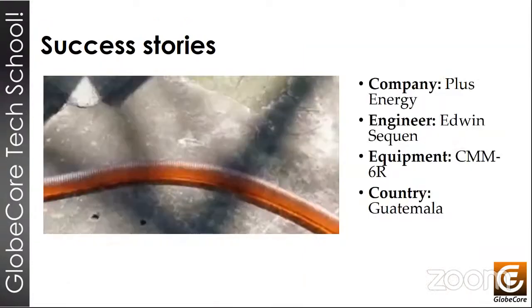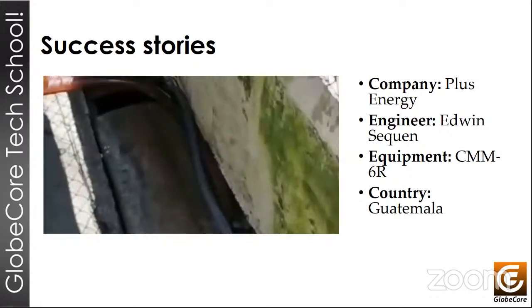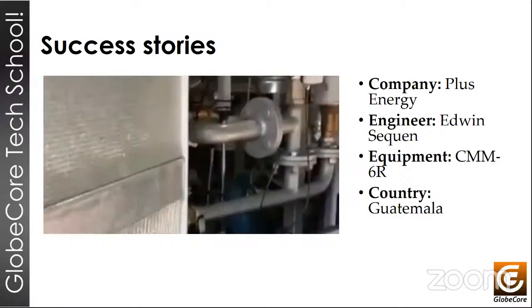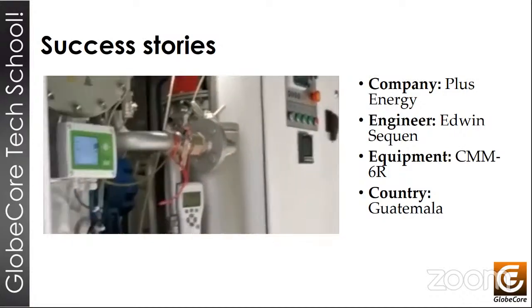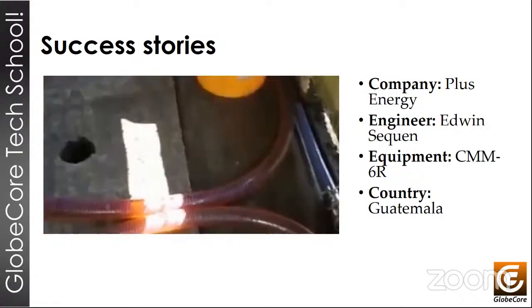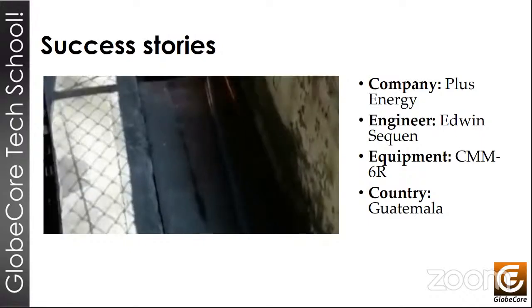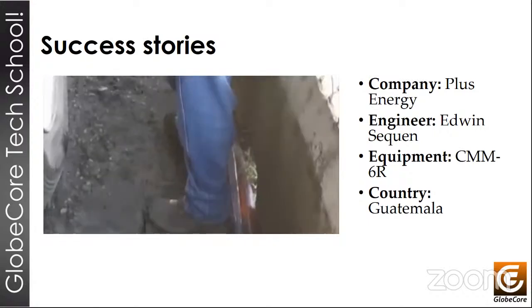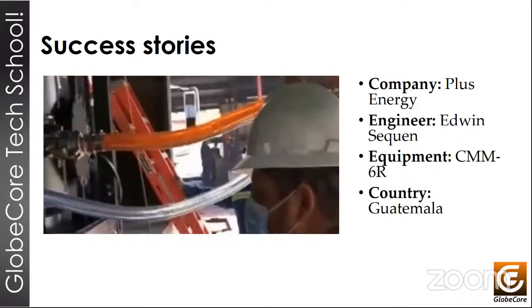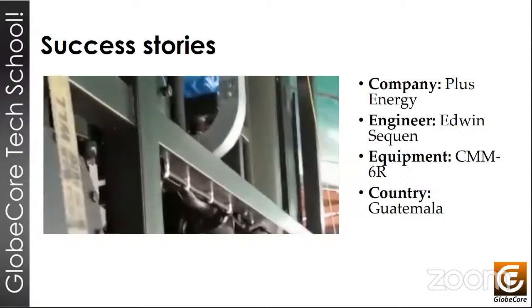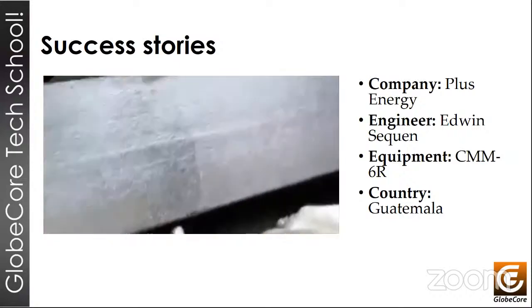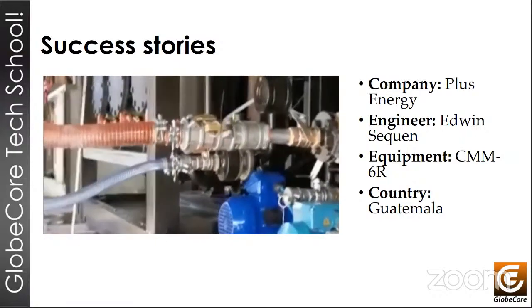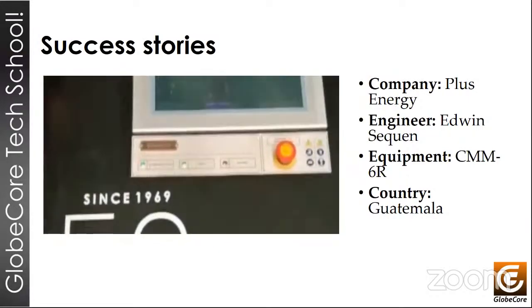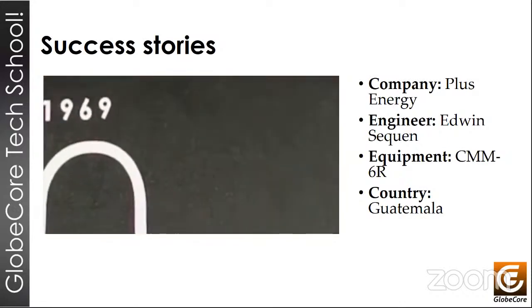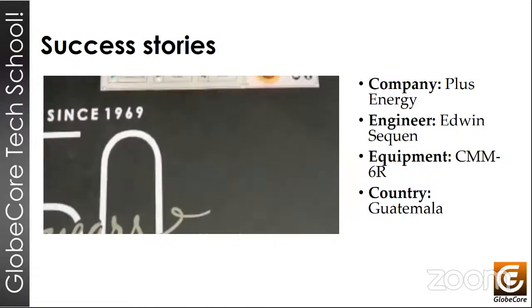Next slide, please. And here we have a little video. This is a project that was done in Guatemala. If you look at the two hoses in the video, you will see the darker one goes into the regeneration plant. This was a 6-column machine with 6 columns of Fuller's earth. Also, this plant includes a vacuum degasser for purification. These columns contain Fuller's earth, and towards the end of this presentation, we'll talk more about this. Here's the control panel, or just a little bit of it. It's a touch screen panel for control. The processes are largely automated.